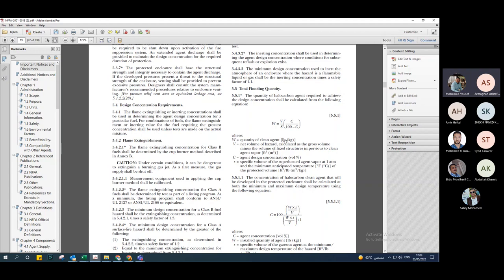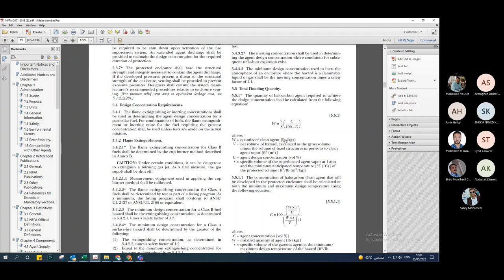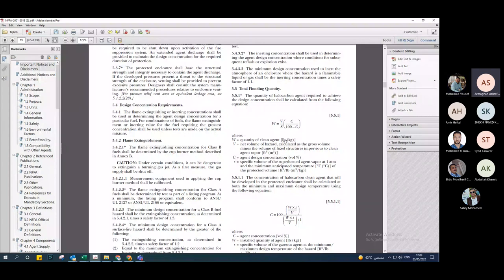The quantity of clean agent in kilograms equals the net volume of the hazard. It's very important to know that the net volume is calculated as the gross volume minus the volume of fixed structures impervious to clean agent vapor. If I have a column or beam in the room, I have to remove it from my volume to get the net volume.